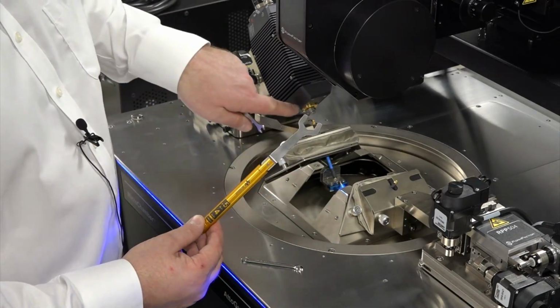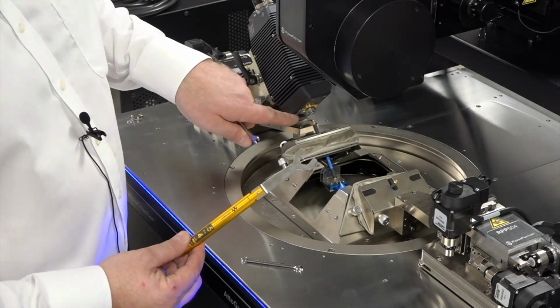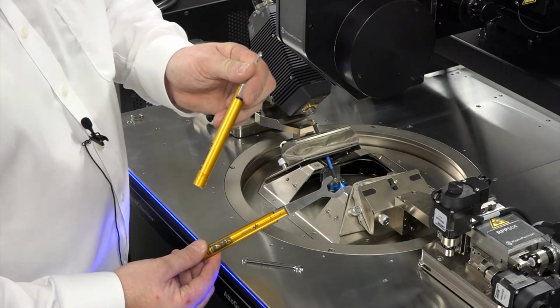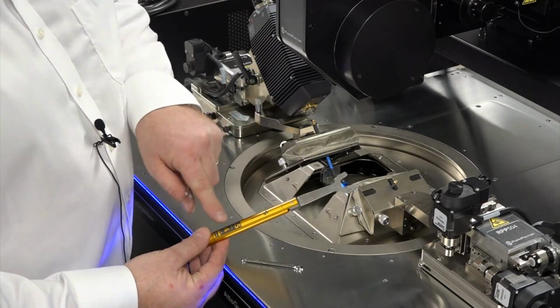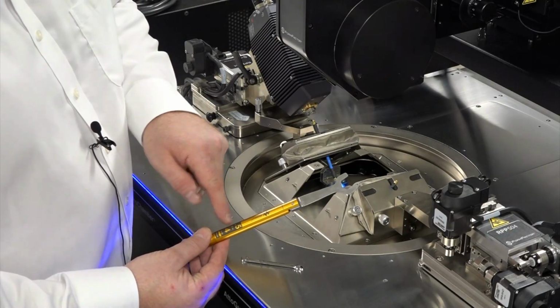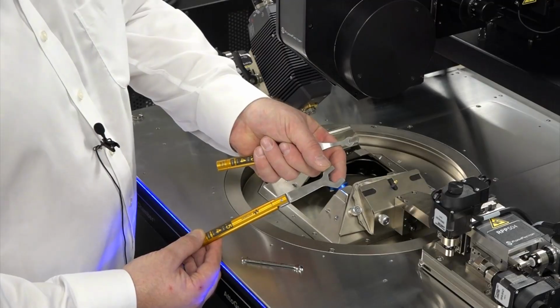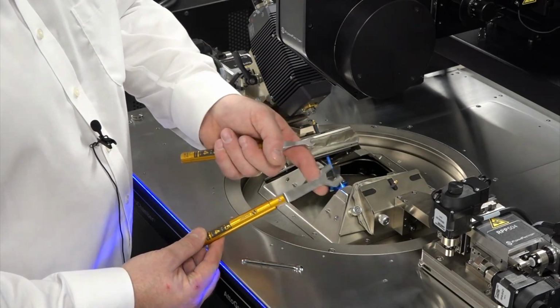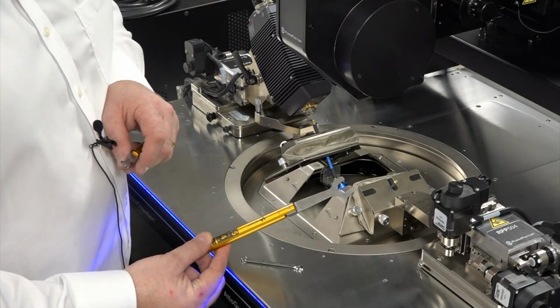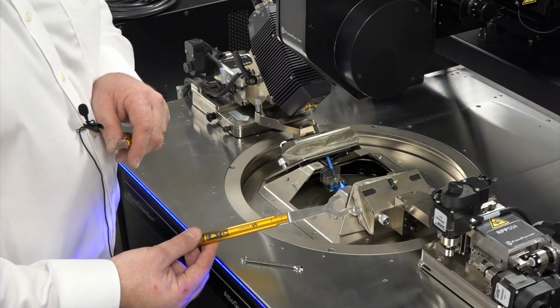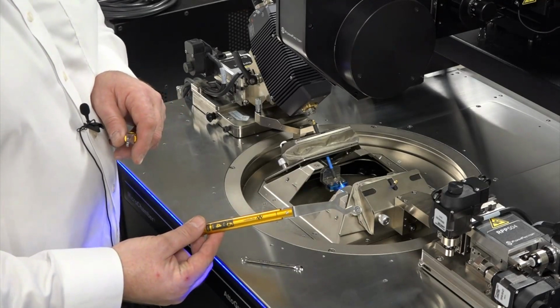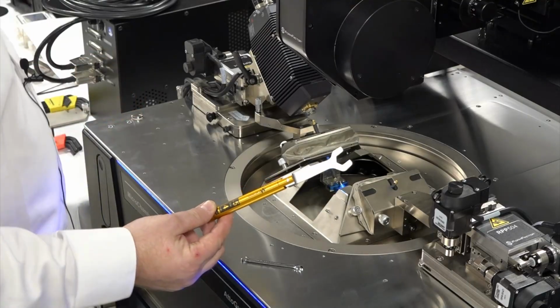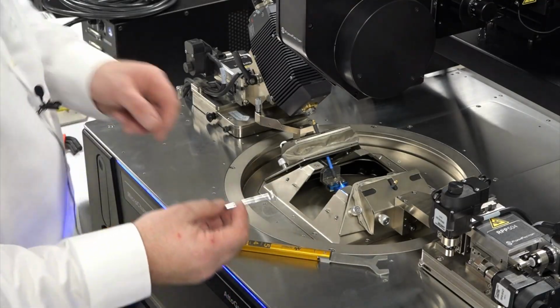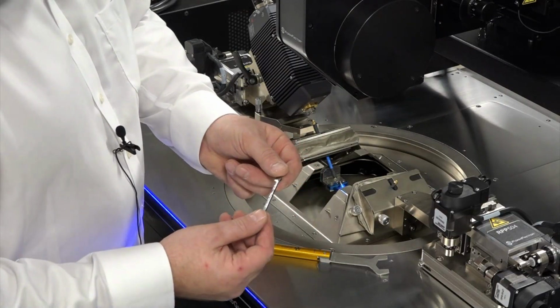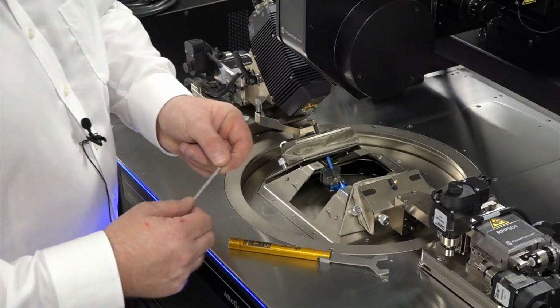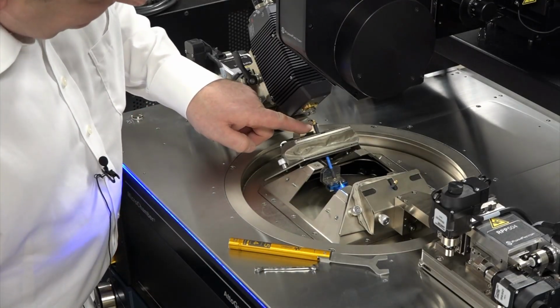What you will be using with this frequency extender is just for the extender end only. The probe end still takes this one, the small one, but for the frequency extender you'll have the same torque, 4 inch-pound, but it has a 14mm spanner size across it. So you will need to have one of these. I got this one from the Keysight Cal kit, and generally if you've got your instrument as a kit it will come with one of these, but you do need one to properly set the instrument up. The other thing I've got here is a spanner for anti-rotation, and this one says it's 5/32. This is to go on the flat of the cable just here.